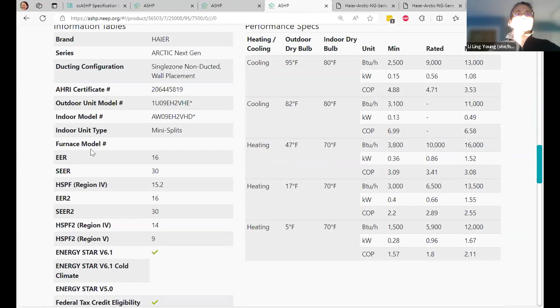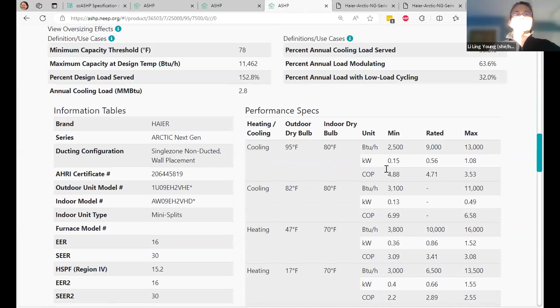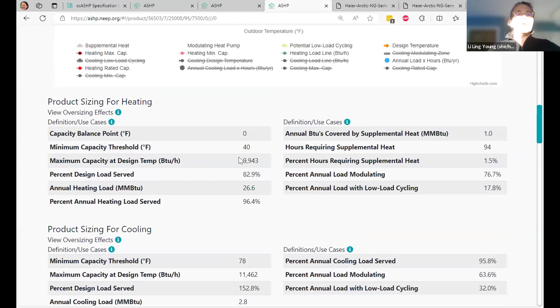I just want to show you, this is the basic search results that I showed at first, but these tables right here come in only after you make the chart. It's showing here that the minimum capacity threshold, this little point right here, is 40 degrees. On those other models, it was 30 and 32 degrees. So this is better. It's also showing what percent of the energy in the course of the heating season is going to be consumed under those short cycling conditions, and it's only 17%, 18%, which I consider to be acceptable.